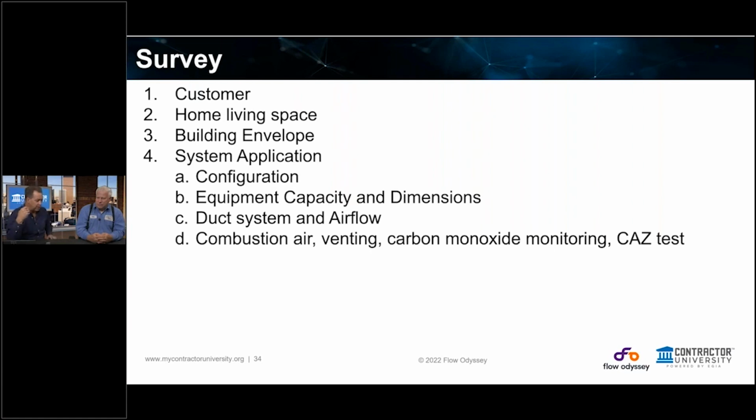He's at the top of the hotel, and they're replacing the plate glass windows at the top of the hotel, and the signal goes off in his carbon monoxide monitor, and he goes to the front desk and tells the manager, hey, you need to stop all construction right now. You've got huge amounts of carbon monoxide pouring into the building through the elevator shaft. You're going to possibly make a lot of people sick or possibly end up killing somebody. And he proved it to them. They shut down the whole project until they could find a way to ventilate it.